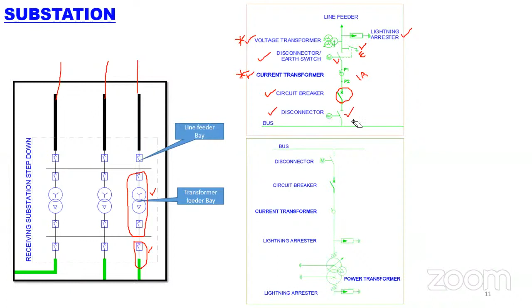Okay, that will be covered in the upcoming slides. Let's just understand the components, then we'll move on. So now the disconnector is going to help when this breaker is in off condition. So this disconnector and the line disconnector will both be open, so that the circuit breaker can be taken for maintenance or control system failures, or you can replace the circuit breaker, which helps a lot. All the components we call switchgear, which is part of the line feeders. Let's take the transformer feeder, then let's understand all.